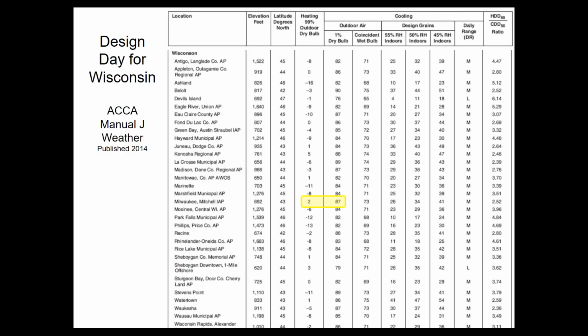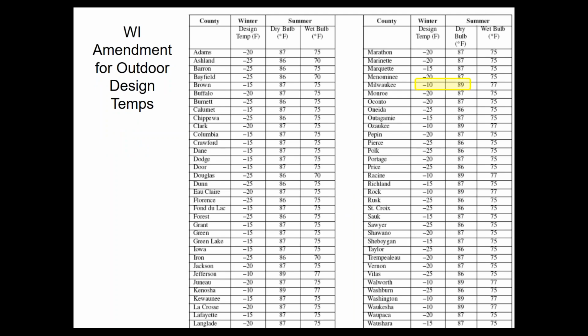If I was looking at the Wisconsin data and I picked Milwaukee, because most of the guys on this call happen to be from the Milwaukee area, my temperatures would be 2 for heating and 87 for cooling. However, you are not going to use the ACCA Manual J for energy code compliance if you're in Wisconsin. There is a Wisconsin amendment to the energy code that says you have to use this table instead.